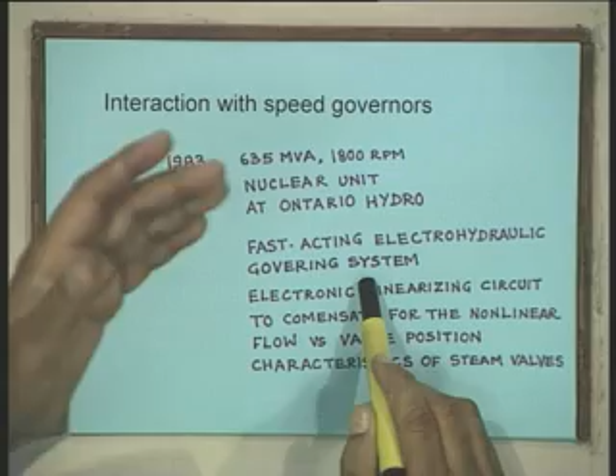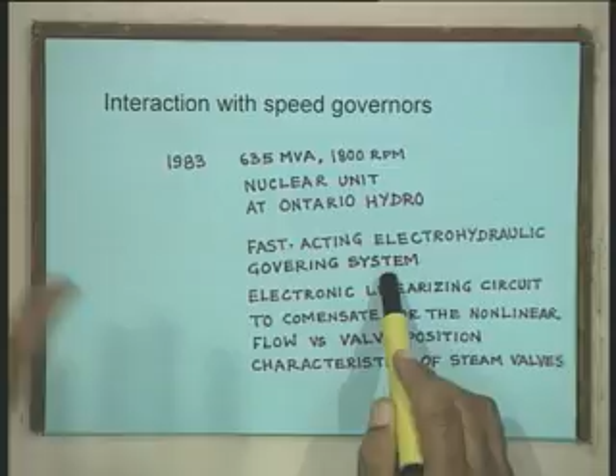The difference in this unit was that it was equipped with a fast acting electro hydraulic governor system, because we may have the mechanical control system, and we may have a fast acting electro hydraulic governor system. In these electro hydraulic governor systems, which are now provided in most modern turbines, the low power functions are performed using electronic circuits, that is, the speed sensing and certain processing is done using electronic circuits. One of the important processing steps is that they use a linearizing circuit to compensate for the non-linear flow versus valve position characteristic of the steam valves. That is, if you plot a characteristic relating the steam valve position to the steam flow, it is a non-linear characteristic, and to compensate for it we provide an electronic linearizing circuit.